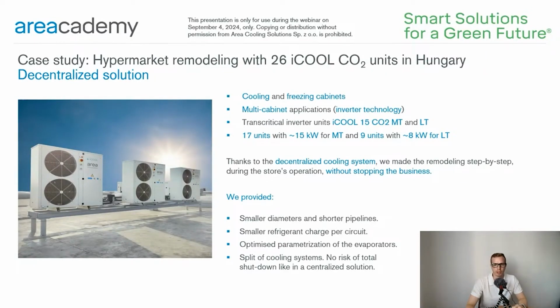And the last case study I want to present is about the decentralized solution. Area Cooling Solutions performed remodeling of a 4,000 square meter hypermarket located in Hungary. The entire installation has been divided into smaller separated sections. A total of 26 iCool CO2 units were installed, finally: 17 units for the MT applications and 9 units supplying freezing applications. Thanks to the decentralization, the customer received increased reliability and better quality of the product. And the biggest decision driver for the final customer was that the remodeling process was done step by step without stopping the business.